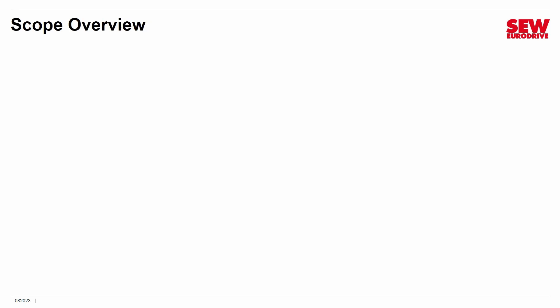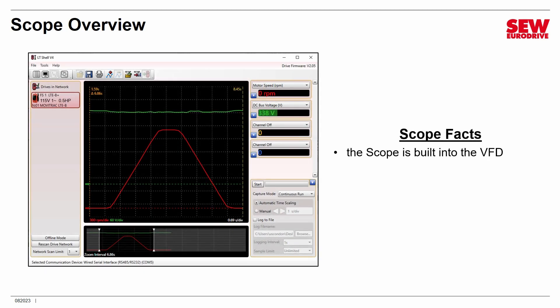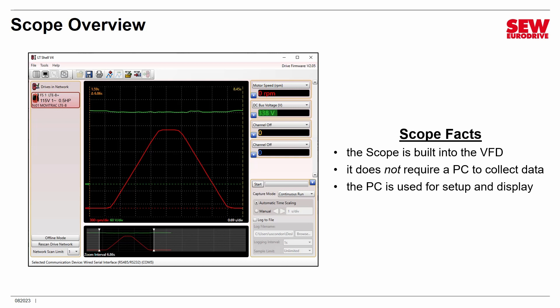Let's overview the scope a little bit. A few facts: the scope is actually built into the VFD. You use LTShell to display the data from it, but the scope hardware is inside the VFD, not the PC. That's very important — the scope does not actually require the PC to be present to do its job. The PC is only used for setting it up and displaying the data. You can configure the scope, close LTShell, disconnect, and walk away, and the scope is still within the VFD doing its job. When the right conditions come, it will collect data. You can then come back later, plug back in, start up LTShell, download the data, and look at it on your PC.